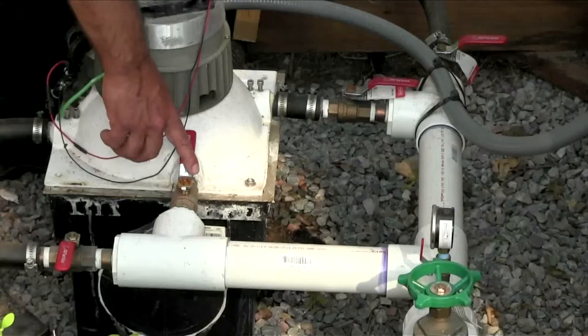This 4 nozzle turbine is a little bit overkill on this site and would produce about 1,000 watts under ideal conditions. The homeowner doesn't need that much, so they've closed 2 of the turbine nozzles and operate closer to their needs. Still overproducing, but not so much that the turbine is getting a bunch of unnecessary wear and tear. So turbine bearings, cleaning the screens, and just general inspection of everything occasionally is all helpful.